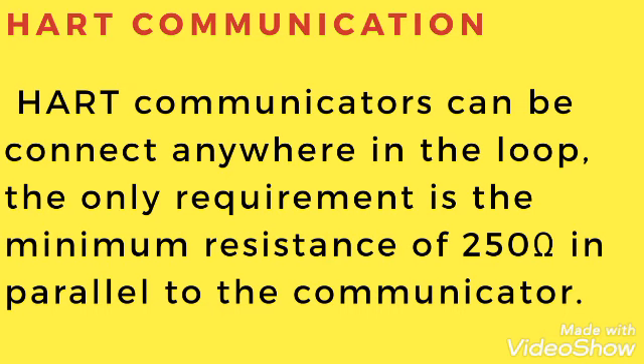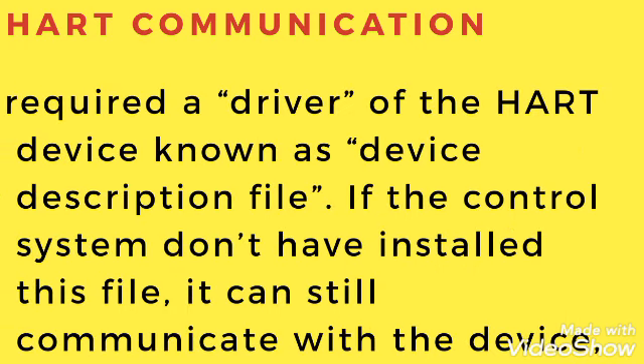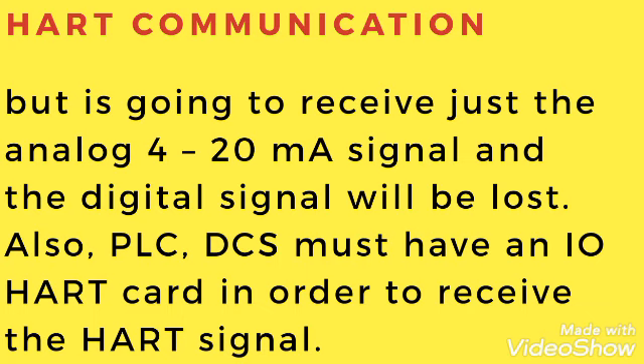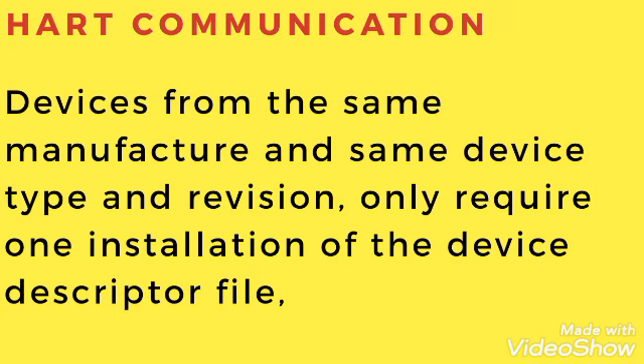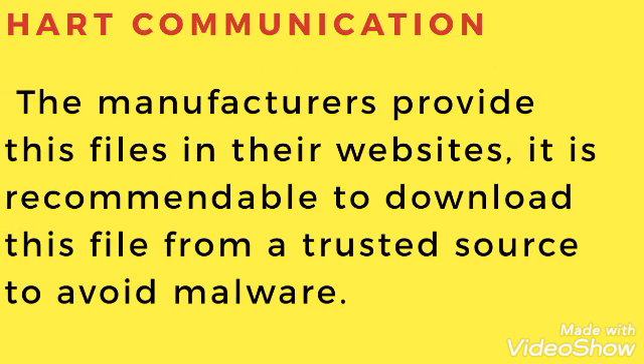A HART handheld communicator is used to calibrate or configure the device. HART communicators can be connected anywhere in the loop; the only requirement is a minimum resistance of 250 ohms in parallel to the communicator. A driver known as a Device Description file is required. If the control system does not have this file installed, it can still communicate with the device but will receive only the analog 4-20mA signal and the digital signal will be lost. Also, PLCs and DCSs must have an IO HART card. Devices from the same manufacturer and type only require one installation of the Device Descriptor file. Manufacturers provide this file on their website, and it is recommended to download it from a trusted source to avoid malware.